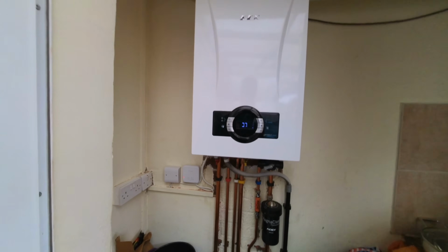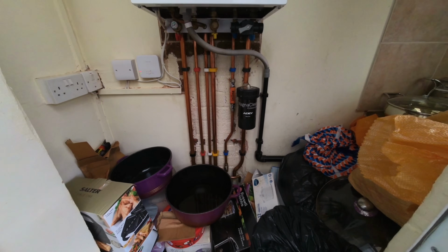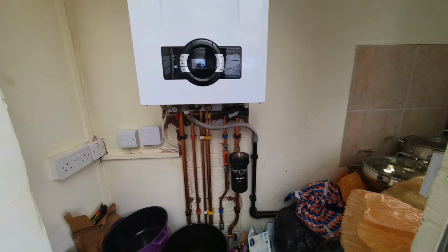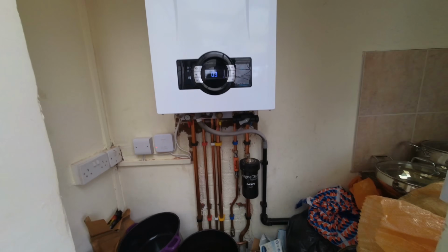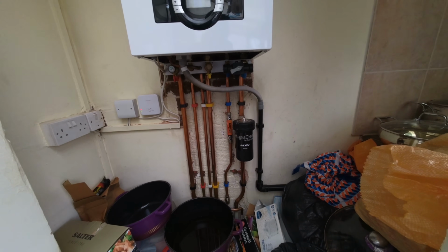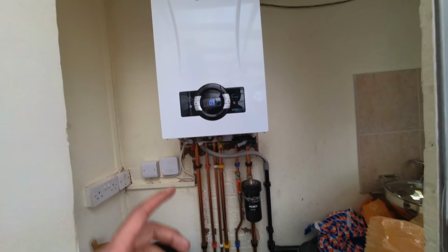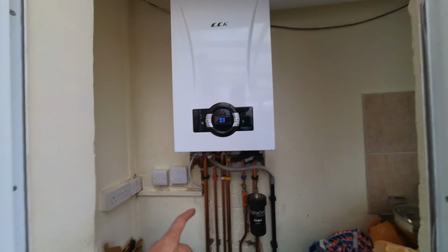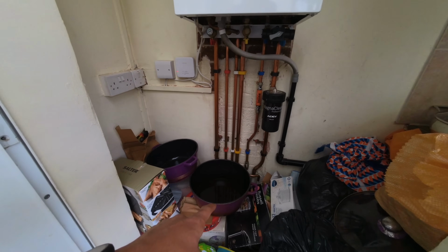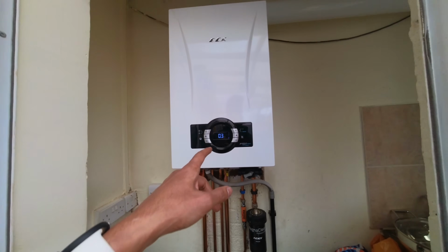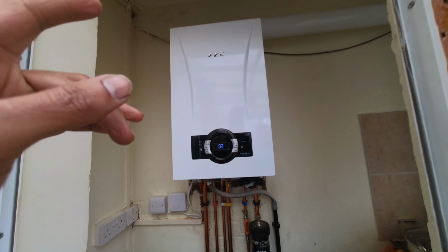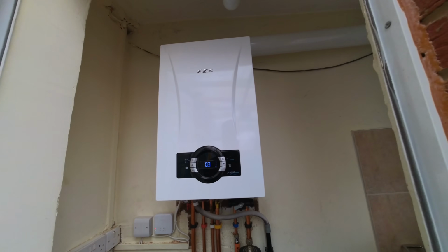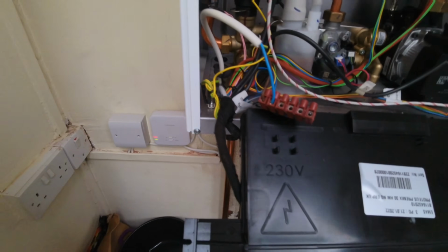We've got an ECA boiler behind me. It's been installed not too long ago, and as far as the installs I've seen from people fitting the ECA boilers, this is actually pretty good - nice straight pipes, clipped and everything, so can't see anything wrong there. But they've mentioned the boiler's been leaking. There's a couple of saucepans full of water there. F37, low pressure, and it's tripping the electrics. So let's open up and have a look, see what's going on inside.